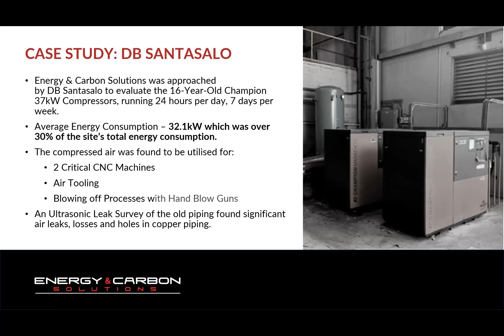Next slide, please. Okay, so what did we do? The energy and flow metering indicated, as Michael suggested, we had significant system losses. We had poor system control. We had load unload on a very inefficient 16-year-old compressor. The compressors were running 24 hours, 7 days a week, just in case they're required. And the compressed air was used mostly in tooling. However, we did have a critical use, which was 2 multi-million-dollar CNC machines that required compressed air when they ran for 2 or 3 days straight.